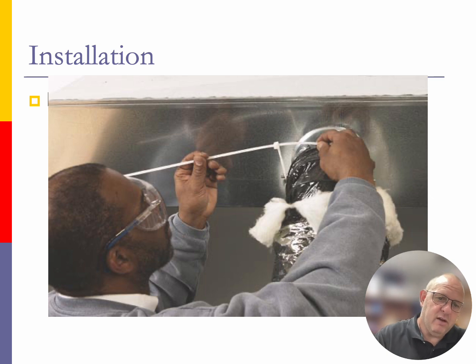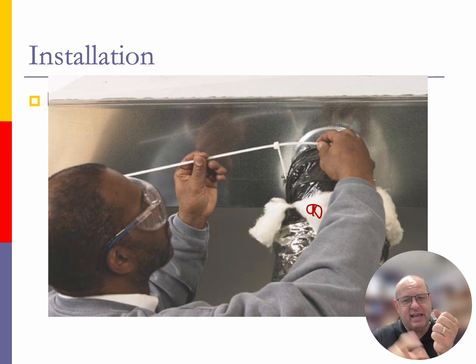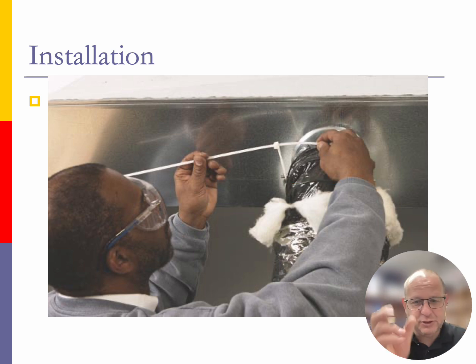We'll take that foil and we'll take that insulation and we'll peel it back and we'll expose the vinyl inside that has that wire that's rigid. And that wire, you can see that wire right there around our particular pipe that's on there. So that wire is what's going to give that vinyl its rigidity, that's going to keep it stretched tight so it doesn't collapse in on itself. And then what we're going to do is we're going to stretch it over top of our takeoff.